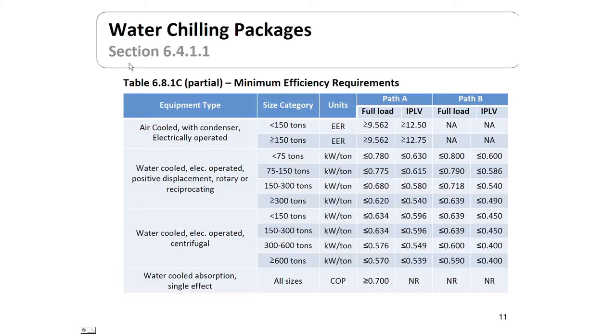For the larger water chilling packages, efficiencies are shown in terms of EER and in some cases KW per ton, based on whether the unit is air-cooled electrically operated, water-cooled electrically operated, or rotary or reciprocating chillers. At the bottom we even have absorption chillers. The chart is divided into size categories in tons of air conditioning, and efficiency ratios are shown for both full load and integrated part load values.